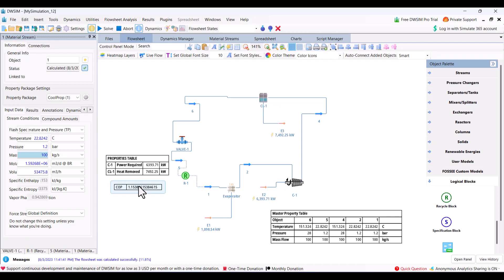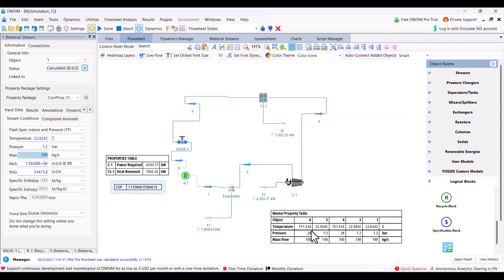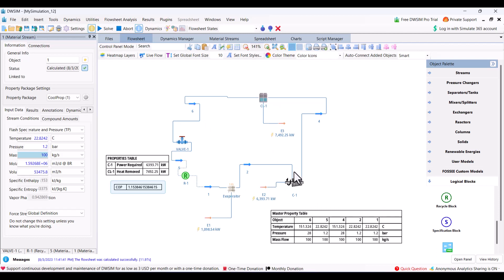Coefficient of heat pump should be greater than 1. Normally it is 2 or higher than 2. There are multiple ways to increase the coefficient of performance. For example, if you see at sixth point after condenser, temperature is still 151 degrees centigrade and we are now using expansion valve and reducing it to 22 degrees centigrade, so there is a lot of heat available which can be utilized to heat water there. So we can add an exchanger there and utilize a lot of heat here. Also you can add a multiple stage compressor to increase the efficiency of compression, and you can also add recuperation which I will explain in later videos. It is very simple to model, and if you have any question you can write it in comments. Meanwhile you can subscribe to this channel for more videos like this.